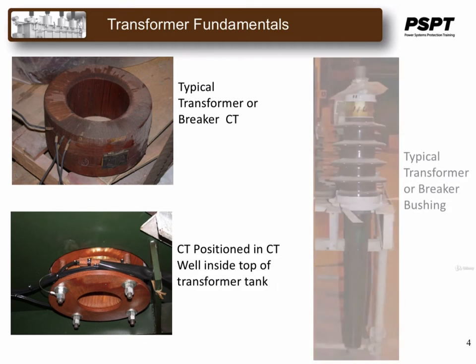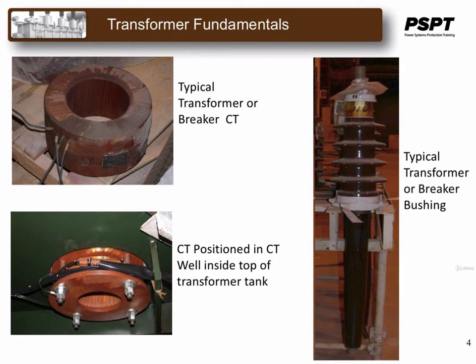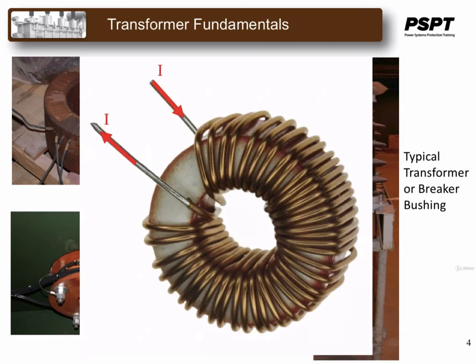These are examples of current transformers that may be found on the bushings of a circuit breaker or a transformer. They are known as donut CTs for their similar look to a donut. The picture on the right is not a CT, but a typical transformer or breaker bushing, which would be mounted through the center of a donut CT. The secondary winding is wrapped concentrically around a toroid, which is usually made up of laminated iron or steel. The primary is a single conductor, usually a bushing, mounted through the center of the toroid.